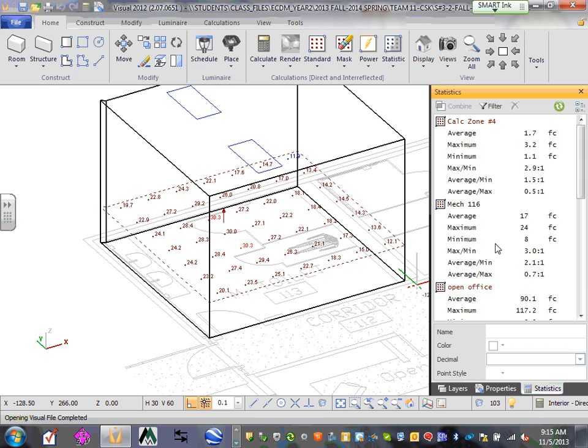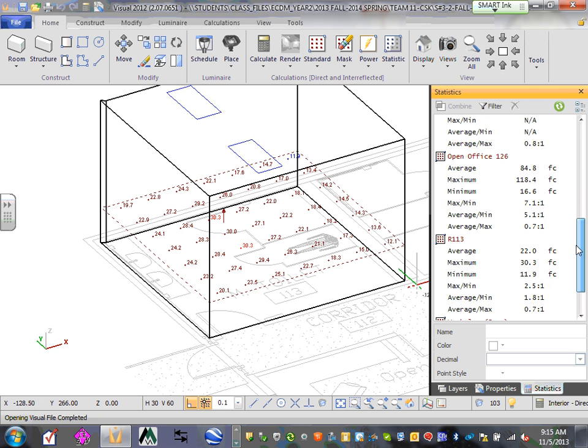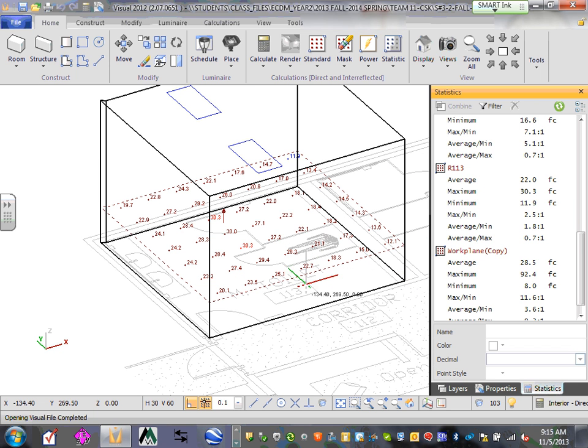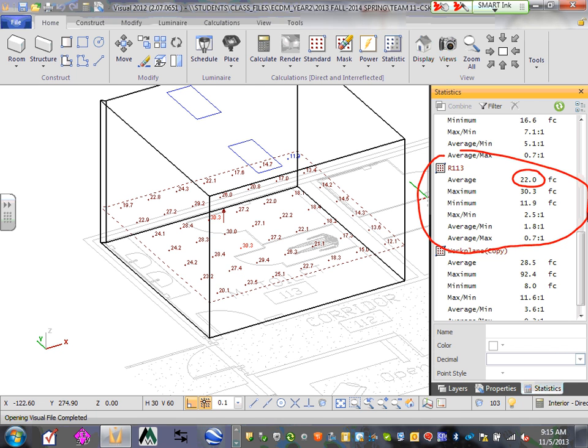The most important part is what we call the statistics. For room 113, the bathroom, it shows the average foot candles is 22. Where you're sitting right now you're probably looking at 50 foot candle average, so you can compare. The maximum is the brightest spot — 30 — and the minimum is the darkest spot. They also give you max-to-min and average-to-min ratios showing light distribution. You care about average, brightest, and darkest so no area is too dark or too bright.